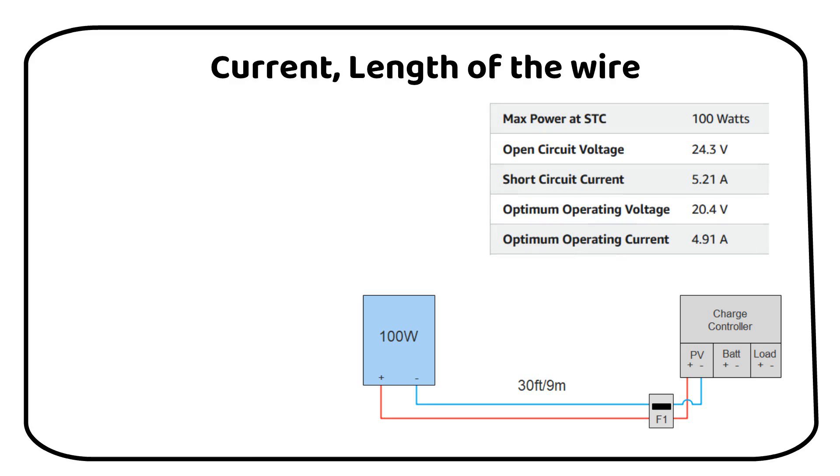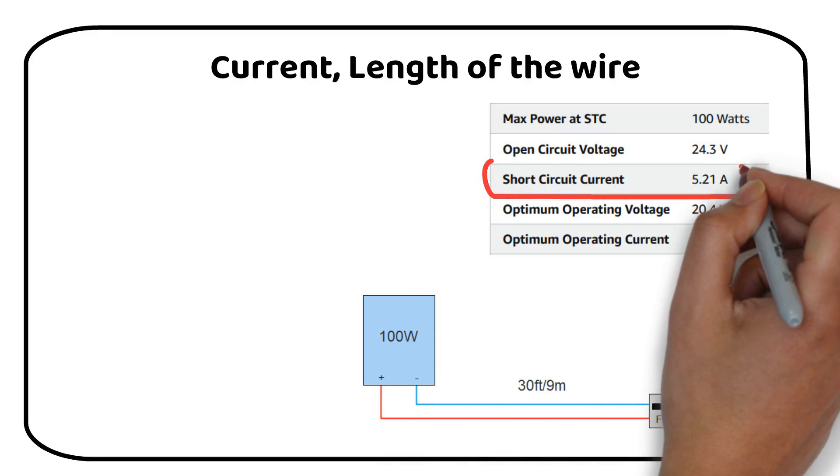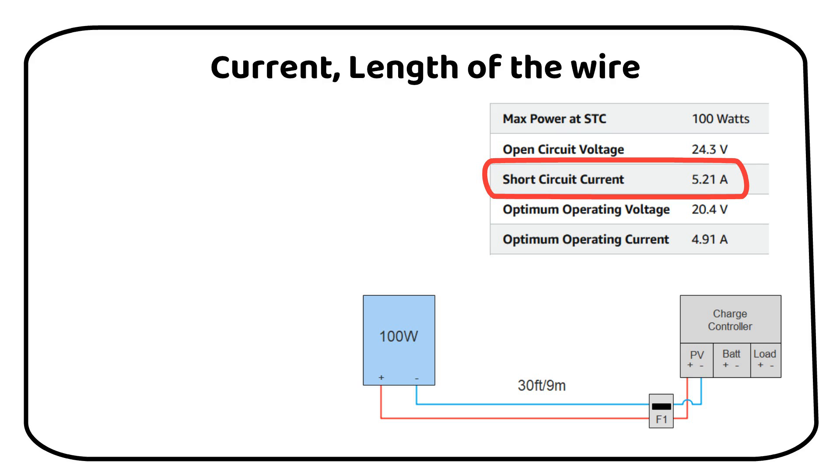The first step is to calculate the maximum current. We look at the panel's short circuit current, or ISC. For this panel, it's 5.21 amps. We apply a safety factor of 1.56 to account for outdoor conditions. This factor is derived from multiplying the standard 125% safety margin by another 125%.